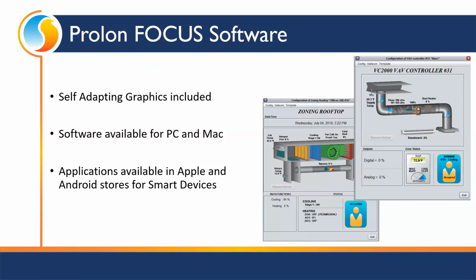Say if I go into this rooftop unit and it is a cooling only rooftop unit, it does not have the capability of heating. If I turn off all of the possible heating outputs, that heating coil will disappear out of the graphics automatically. I don't have to edit, change, or delete anything. It updates automatically. That way you eliminate the confusion of a customer looking at it and saying, well, it's cold in here, why isn't it heating, not realizing there is no heat to heat with.